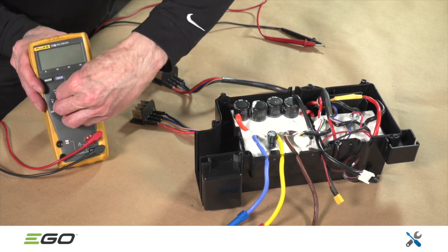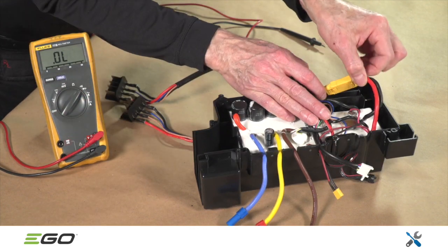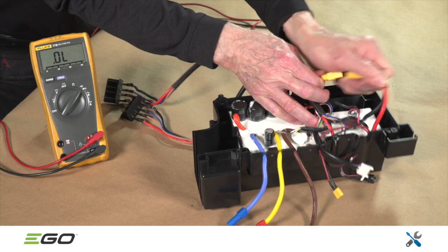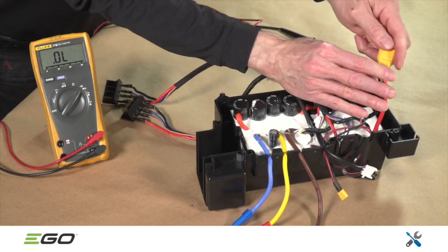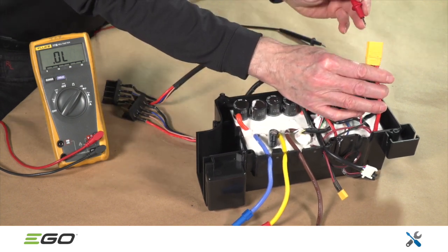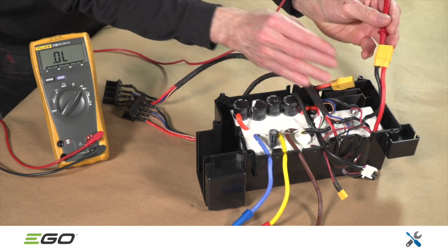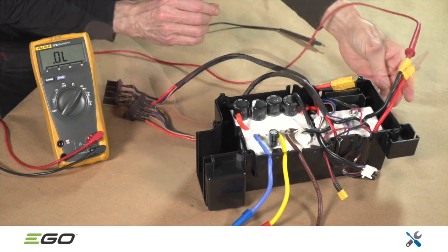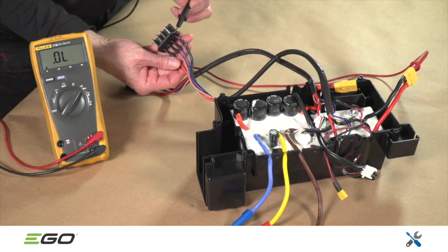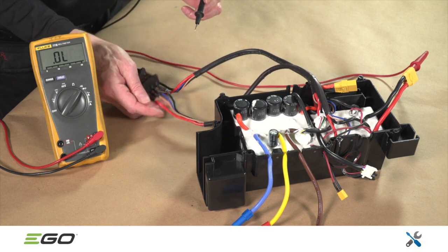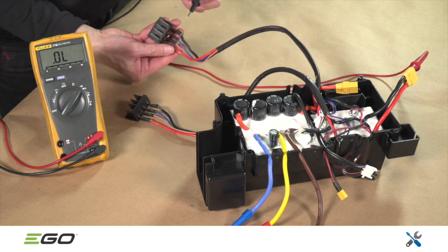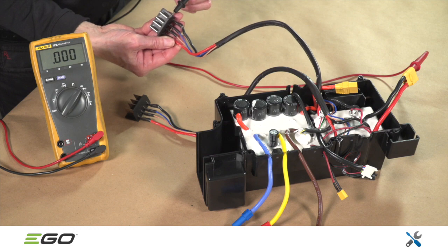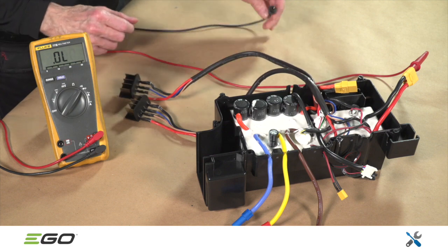Start by checking the fuse. With a multimeter in continuity mode, unplug the larger of the 2 yellow connectors and check continuity between the black or negative blade on the battery connector and the negative output to the main PCBA. Perform this check on both battery connectors. If both connections are good, proceed to the next step. Otherwise, replace the entire control box.